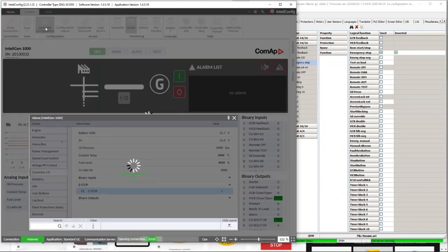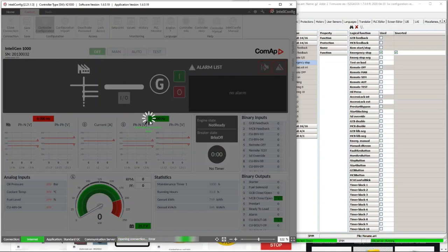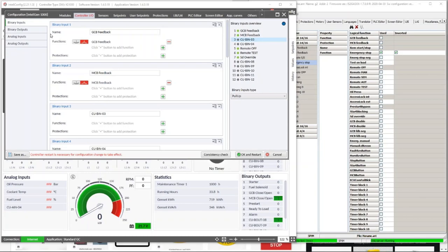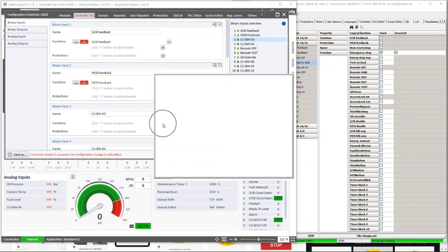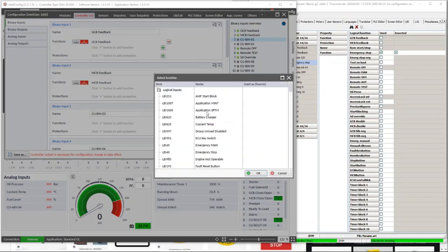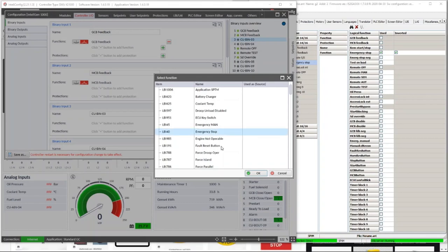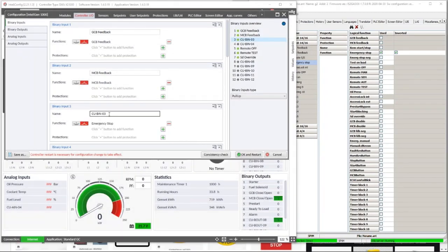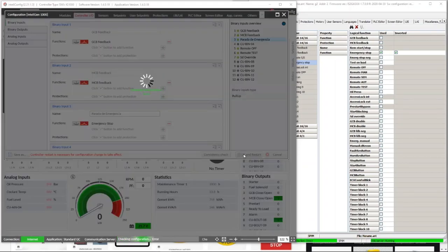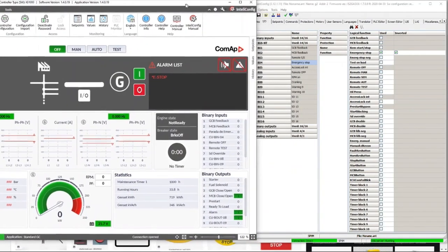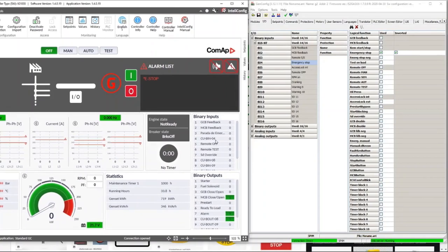In InteliConfig, we go to controller configuration, then we select the binary input we will configure and assign the function that will be emergency stop. Then we press OK and give it the name we want. Finally, we press OK and restart. Once the configuration is loaded in the controller, we will see the inputs configured in the binary input window. Binary input number 3 is the emergency stop function configured now.